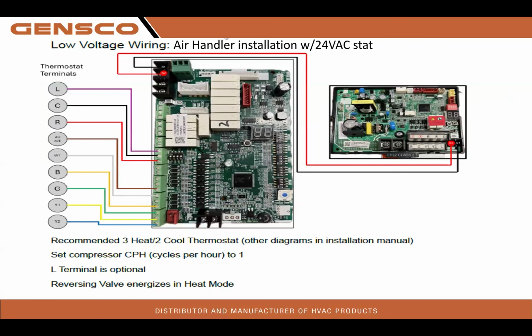Here's a look at our low voltage wiring to the air handler via 24-volt stat. Everything looks pretty normal there. Remember, I was recommending that you use a 3 heat 2 cool thermostat, and I want you to set the compressor cycles to 1. If we were to set cycles per hour to 3 and 4, it's probably going to become an issue in defrost. This equipment likes longer run times at a lower modulation. The L terminal is an optional terminal for alarm, which technically we don't even use anymore. And the reversing valve energizes in the heat mode.